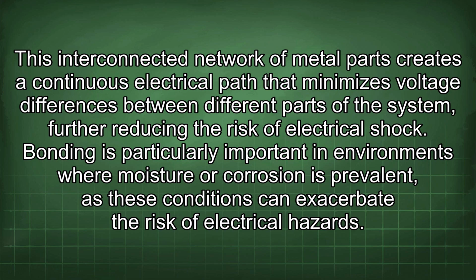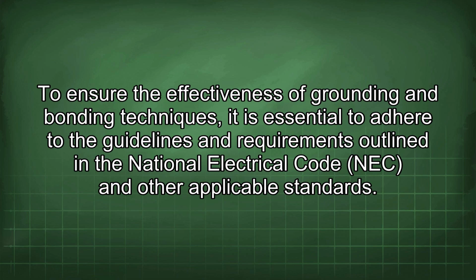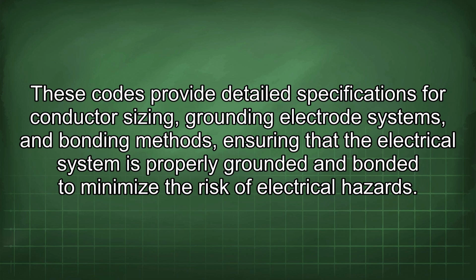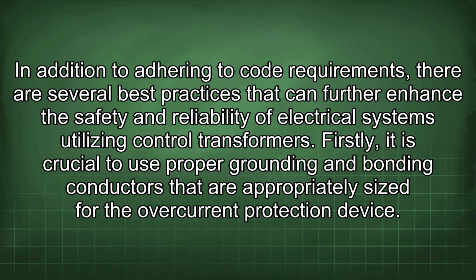Bonding is particularly important in environments where moisture or corrosion is prevalent, as these conditions can exacerbate the risk of electrical hazards. To ensure the effectiveness of grounding and bonding techniques, it is essential to adhere to the guidelines and requirements outlined in the National Electrical Code (NEC) and other applicable standards. These codes provide detailed specifications for conductor sizing, grounding electrode systems, and bonding methods, ensuring that the electrical system is properly grounded and bonded to minimize the risk of electrical hazards. In addition to adhering to code requirements, there are several best practices that can further enhance the safety and reliability of electrical systems utilizing control transformers.